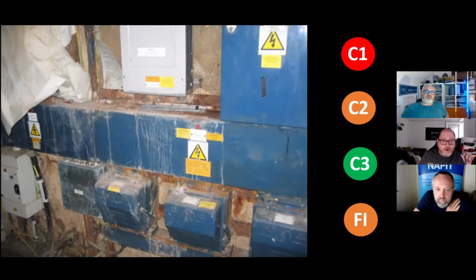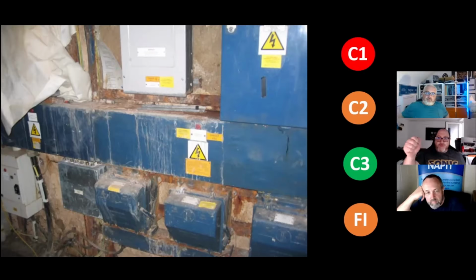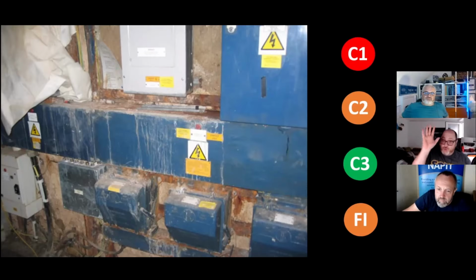I was at a place not long ago, not too dissimilar to this, but you opened up the panel, took the lid off, and the board had no back to it. You could see the wall, it had corroded through the whole board. So you need to investigate. This is why I was taught as an apprentice: in commercial and industrial installations, if you've got any form of porous wall, you mount shallow unistrut. Never forgot it, and I always insist upon it.